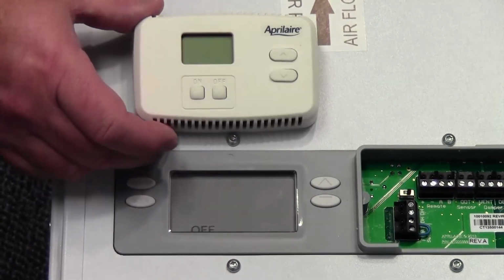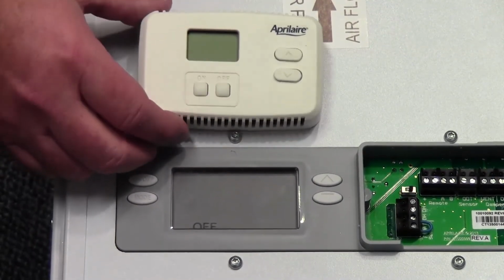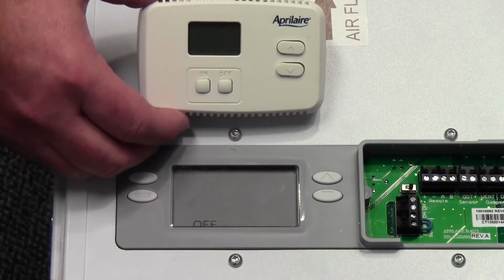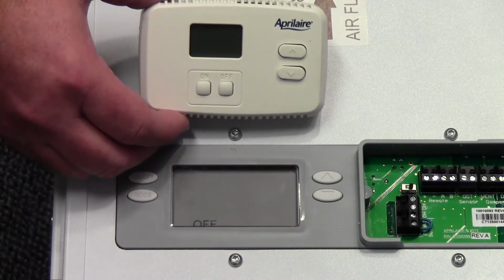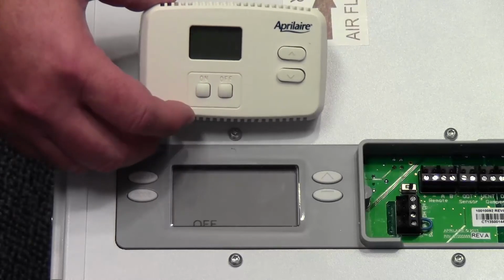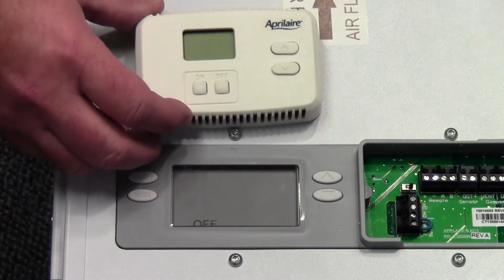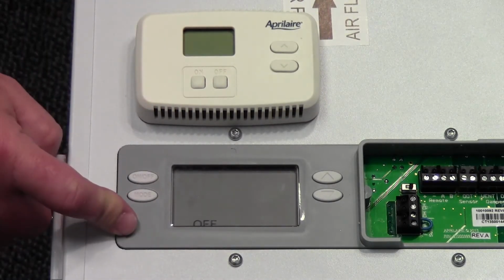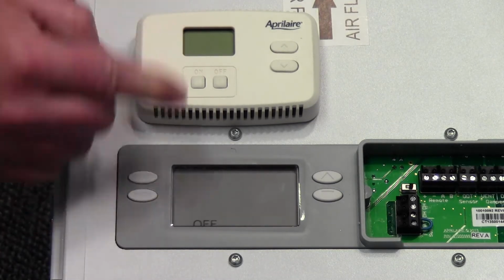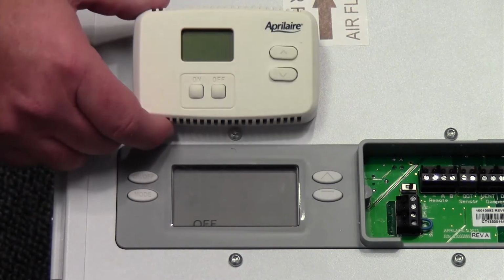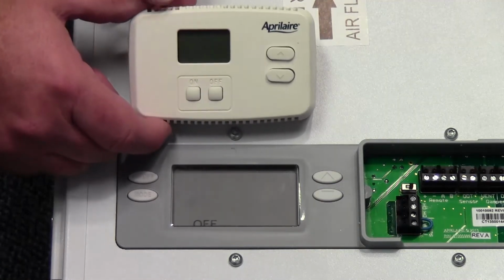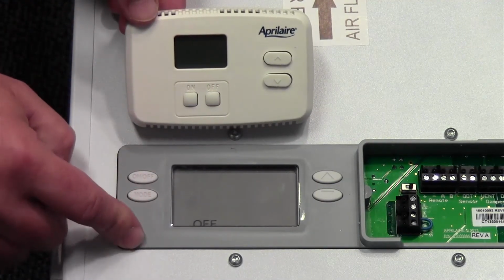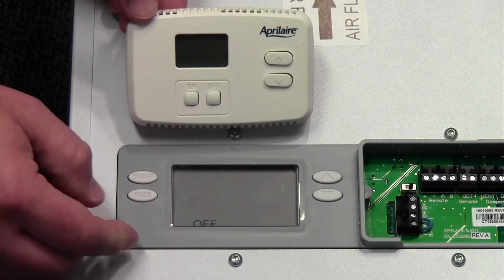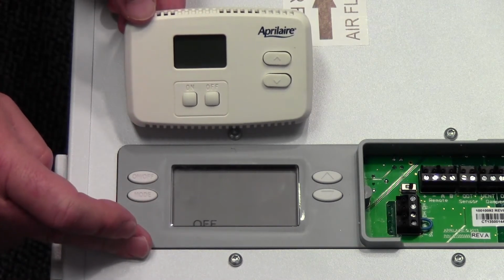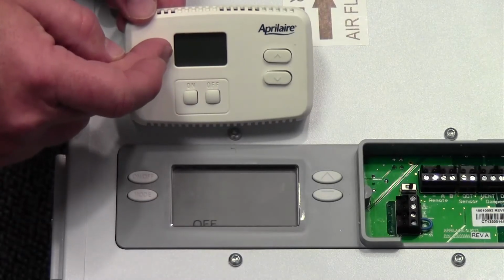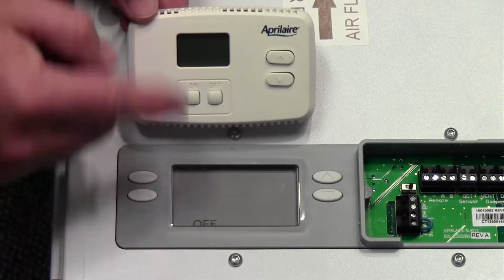Now, if we have an application where we're dehumidifying outside of the building envelope, like a crawl space, or maybe a spray foamed attic, and we want to have control inside of the house, we can use this control as a remote control. And as a remote control, it doesn't disable this internal control, it works with it. They communicate back and forth, so we can actually send a set point down to the crawl space, and the unit will respond and dehumidify to that set point. This control will take an RH reading of the crawl space and send that back up here and have it displayed on the screen. So we work back and forth.